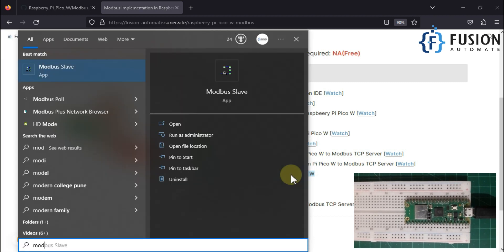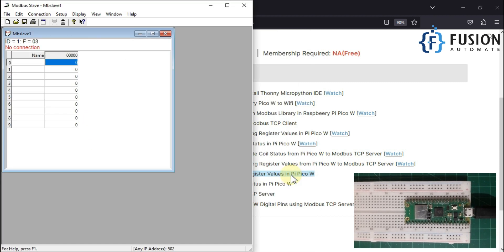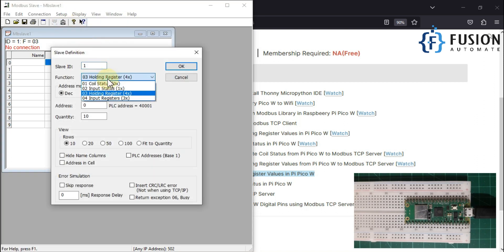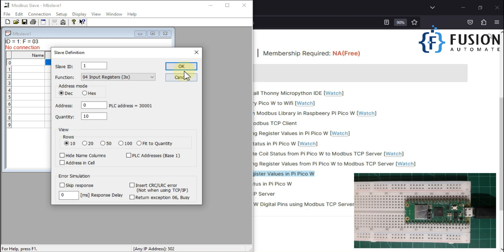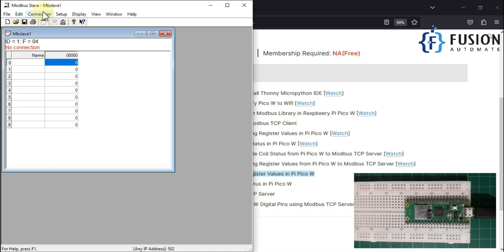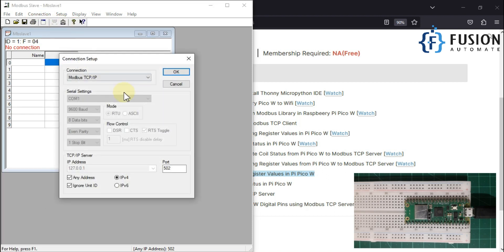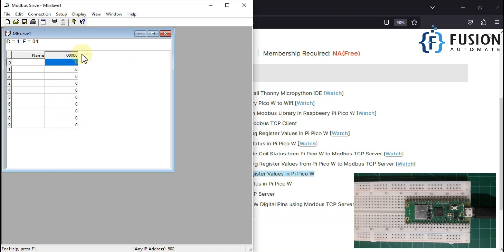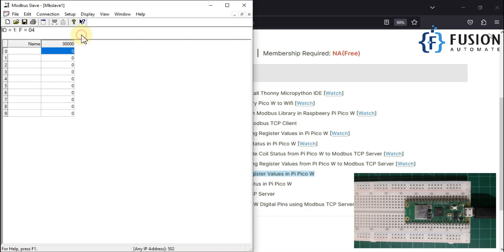First of all we have to set up our remote Modbus TCP device. For that I am going to use Modbus Slave software. I will go to setup slave definition and instead of holding register we have to select input register and then we will press OK here. And connection, and then go to connect, and then our connection type is Modbus TCP IP port number 502 and then we will press OK here.